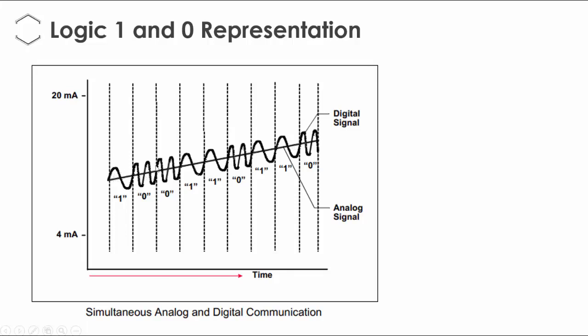But riding along with it and increasing along with it is this signal, but the amplitude of this signal doesn't matter at all. It's the frequency of the signal. So this is our 2200 Hz here, it's a 0, and this wider wavelength here means a lower frequency of 1200 Hz, which represents a logic 1. So 10010. You notice that the frequency constantly shifts as the signal propagates along to represent ones and zeros. So that's why it's called frequency shift keying.